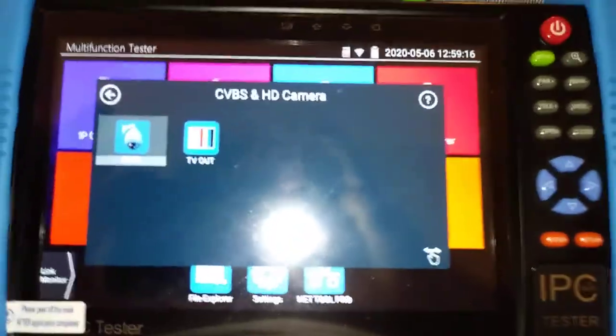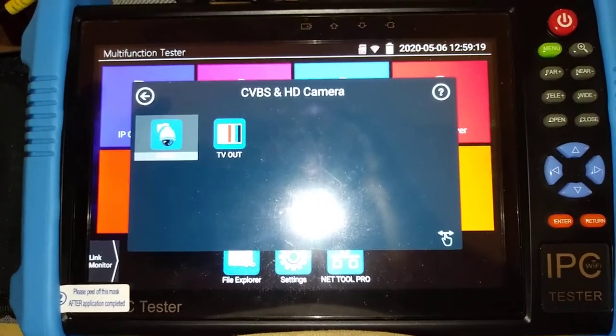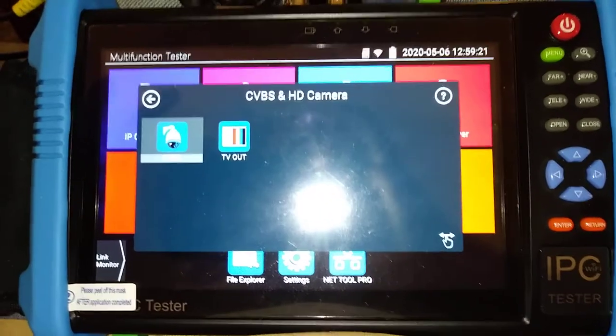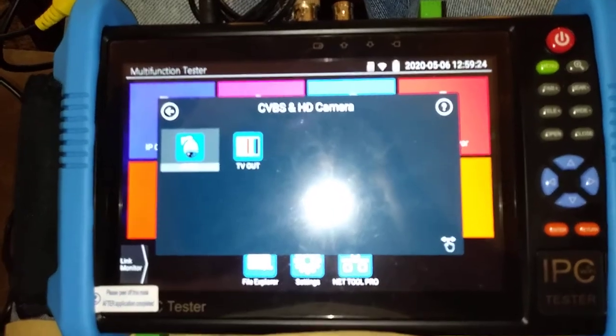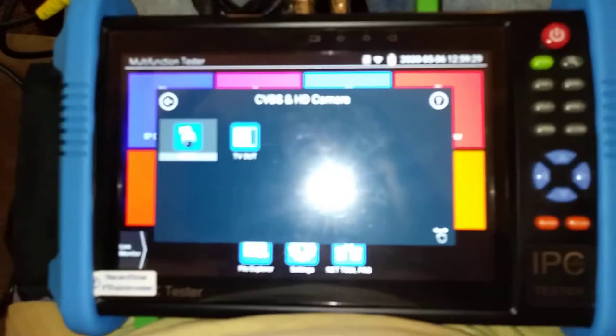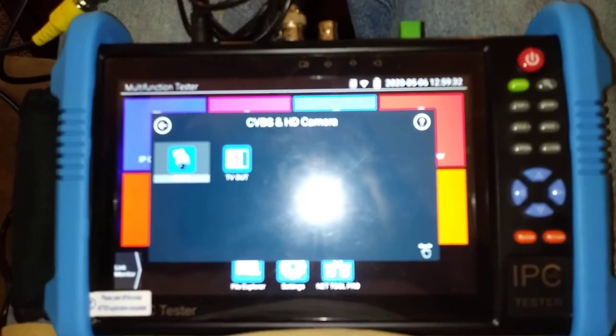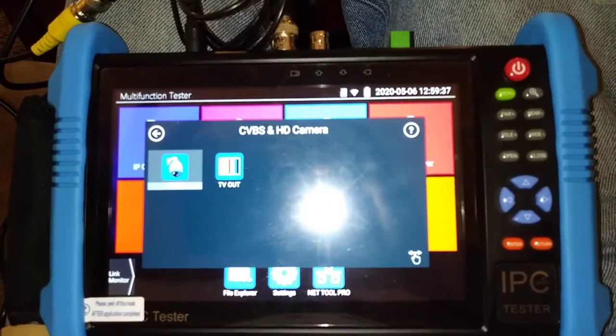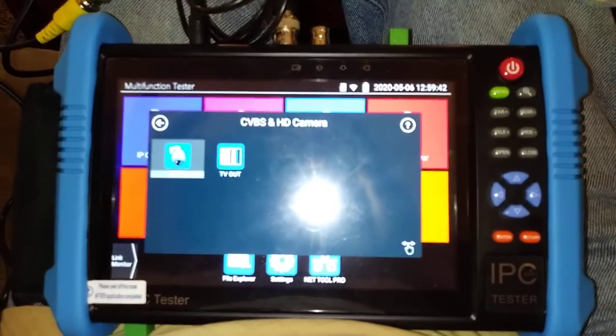This would take over the PTZ functions and make that camera move. That way you can prove from the camera room that the PTZ is or is not working. Then you might decide whether you need a lift to go outside and get access to the wires to verify whether it's something inside or outside of the building. I do have other test procedures on other videos that show you how to work around that.